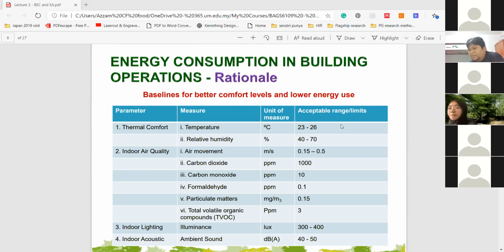Okay. The MGTC building, Malaysian Green Tech Corporation building in Bangi, although it's hailed as one of the greenest buildings in Malaysia, okay, it's a showcase building. It doesn't have any air conditioning. Okay. It only has got this underfloor cooling system, which works fine. Okay. But the problem is, although it absorbs much of the heat from the people and the buildings and whatnot, having said that, there's no air movement because they don't have a blower, to blow cool air all over the place, like the air conditioning, like the ceiling fan.